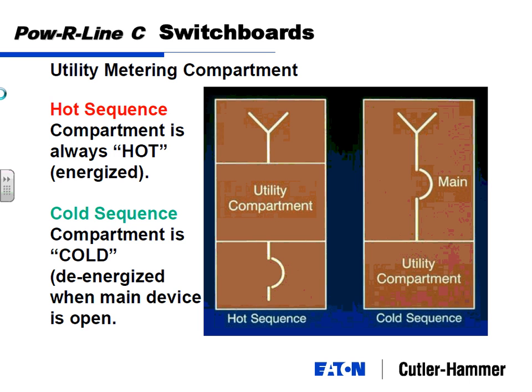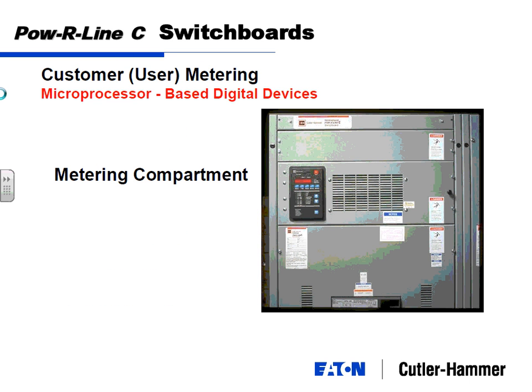What you have to do with the drive-by, you know, they've got the radio type deals that they do all their wireless metering, part of the smart grid now. But are they taking the CT cabinet out or just the meter out? CT cabinet. So you have to have a termination box outside? Yep. Or a 4,000 amp switchgear, that would be a big termination box. You bring the cables in and out. Wow. Yep, that's exactly what it is.